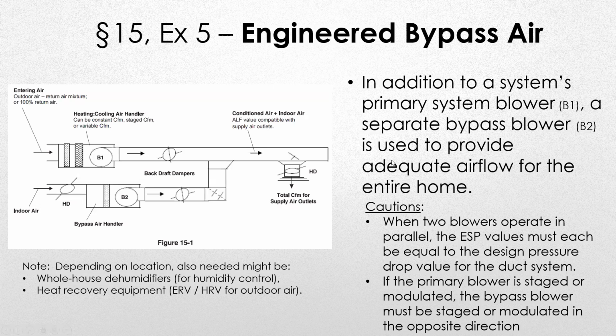And a big note, which they cover in here with this bypass system, is if you're going to use 2 blowers in parallel, the static pressures must be equal to the design pressure drop of the entire duct system. And if you're going to use modulating blowers in there, then they both either need to be staged or modulated in the opposite direction. And the manual goes into great detail over that.